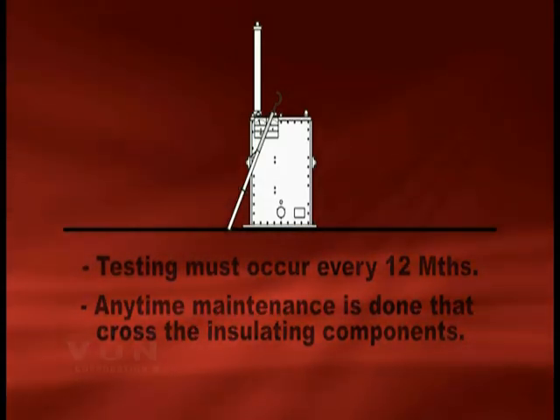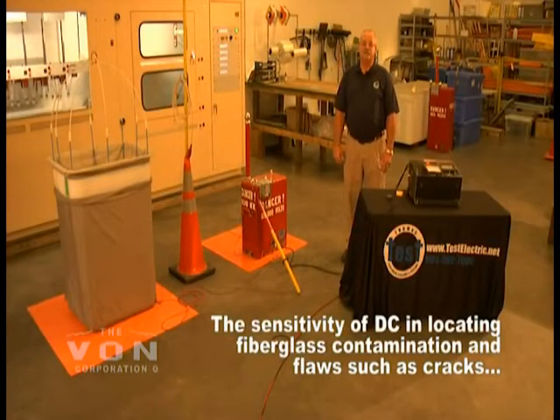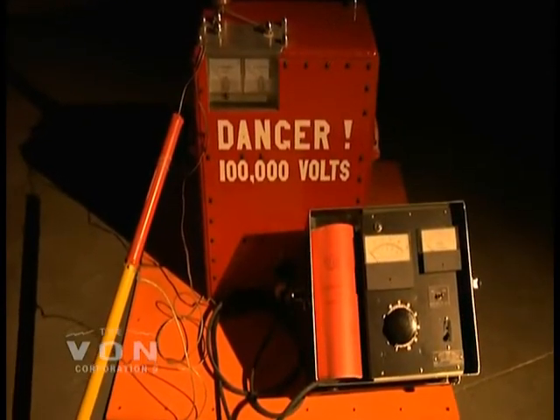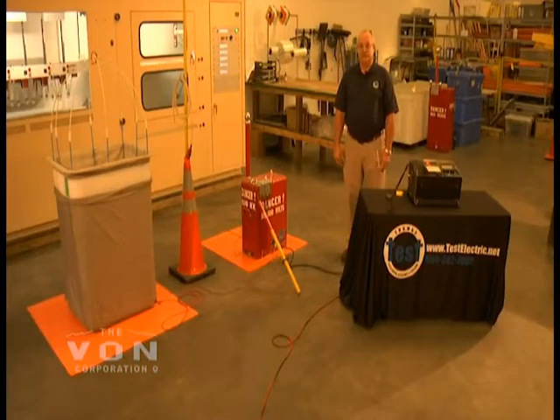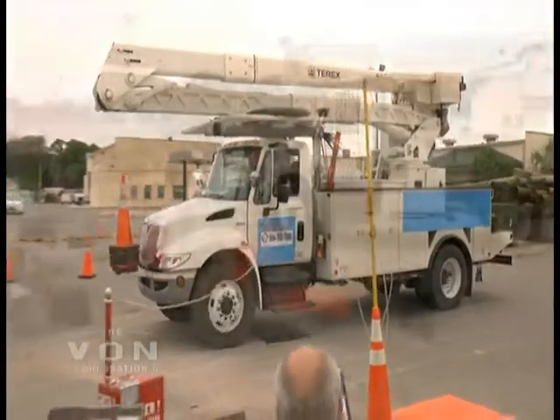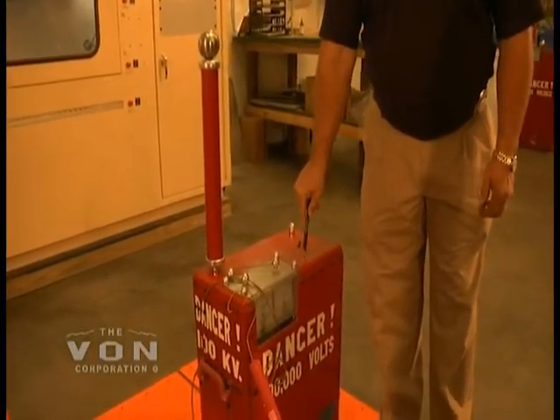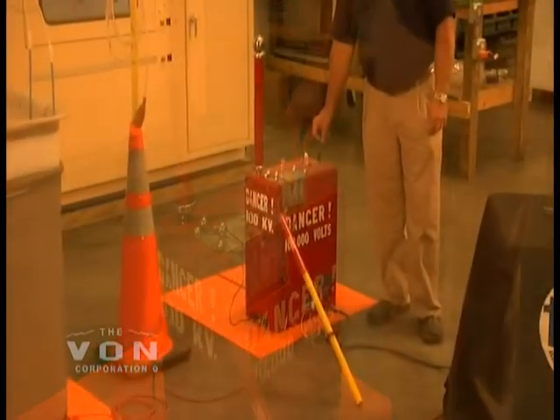The C1 unit is very light. It's very easy to use. It takes minimal people to use it, and it is a DC unit. It runs off of 110 volts, and the C1 will build up to 100,000 volts DC so that you can test your bucket trucks, digger-derrick trucks, and bucket liners with it in this one unit. This is the VON C1 main unit that consists of the transformer and capacitors that raise the voltage from 120 volts to 100,000 volts.